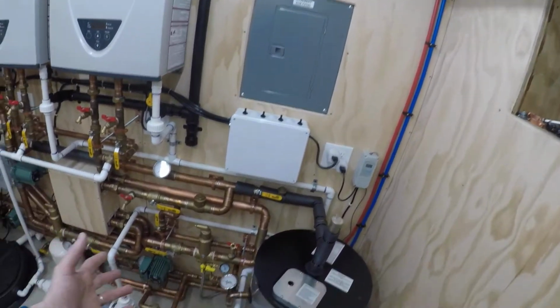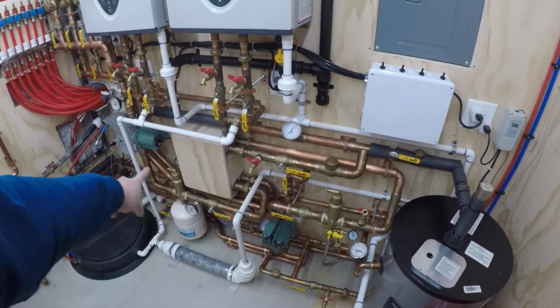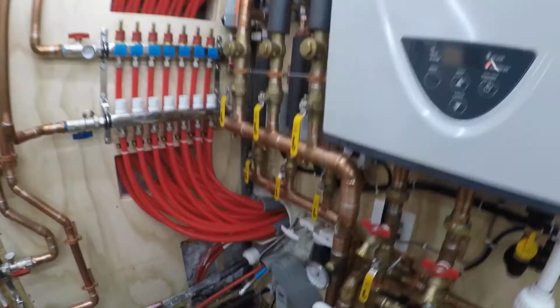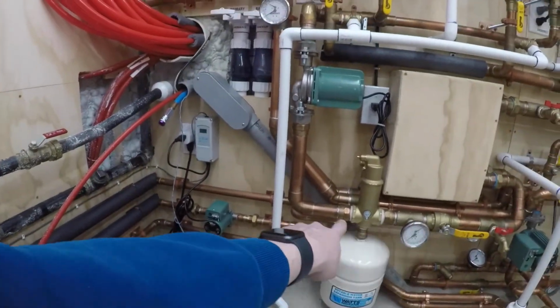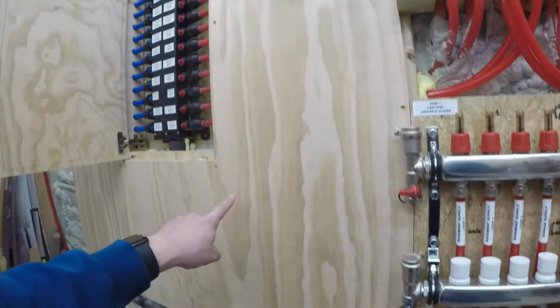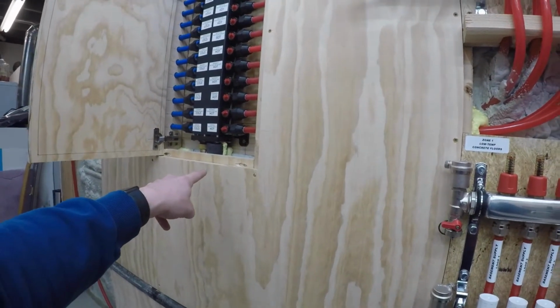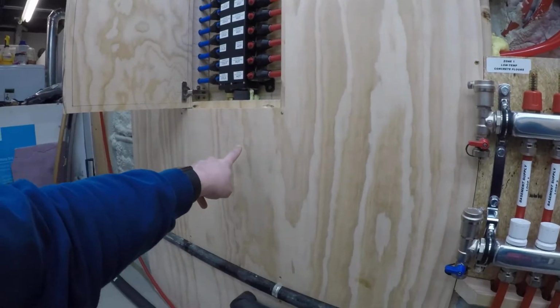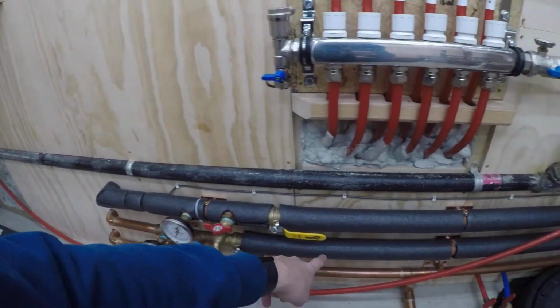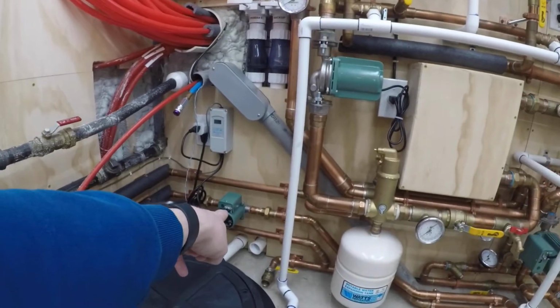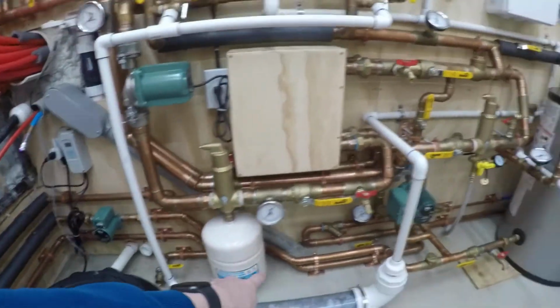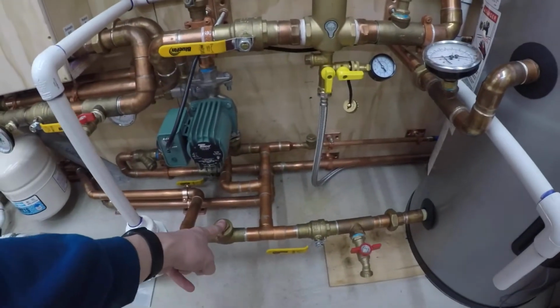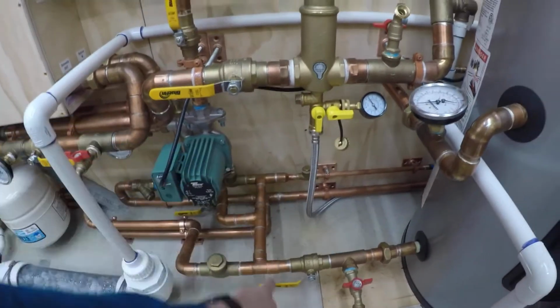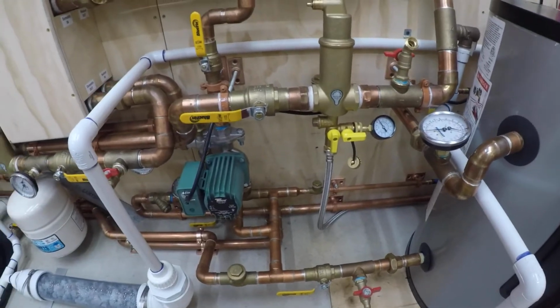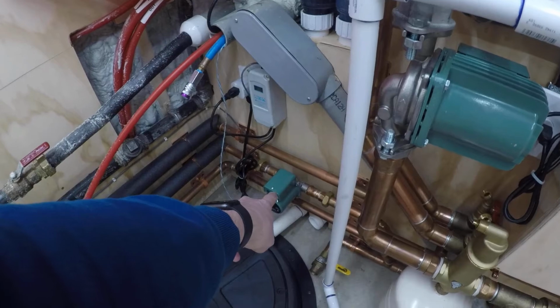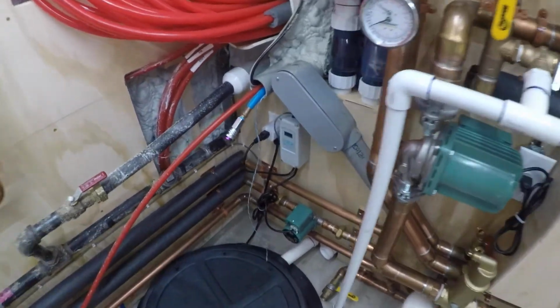So also, I have a hot water recirculation loop here that goes over to that little pump. So like I mentioned, the hot water travels across the top here, goes up and tees in, and then it can either go to the hot fixtures or it can come down and into this middle copper line here, which goes through that recirculation pump, down, over through here, through this one-way check valve, this way only, and back into my neutral area. So right now, this hot water recirculation pump just kicked on.